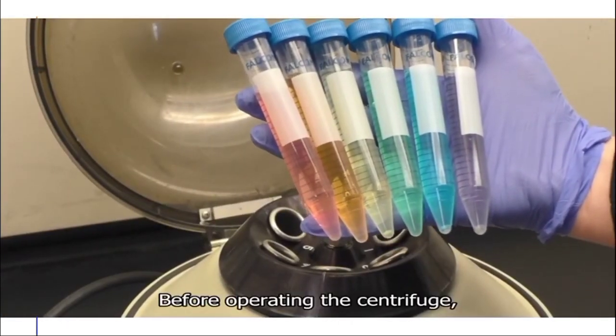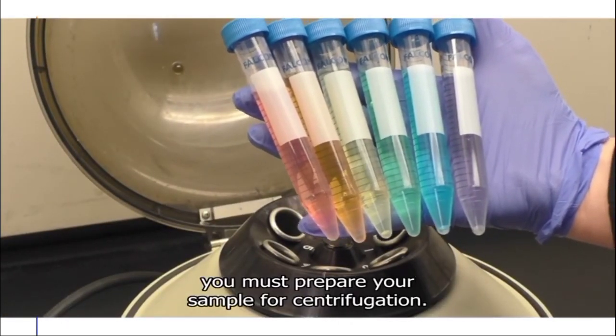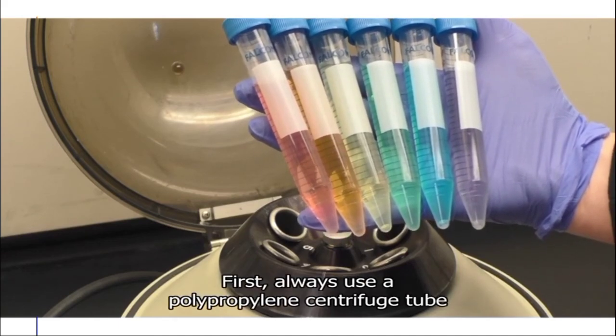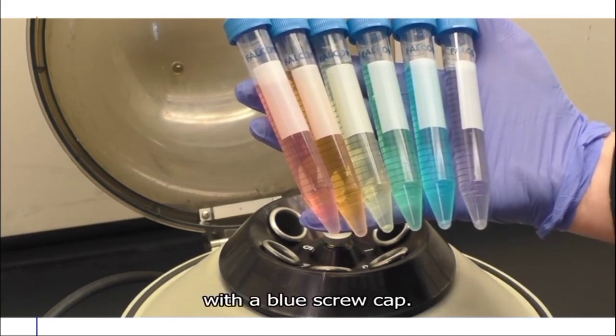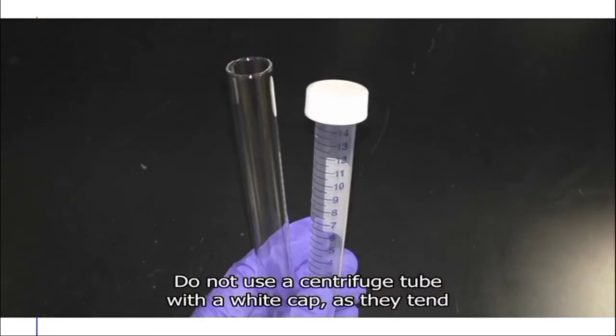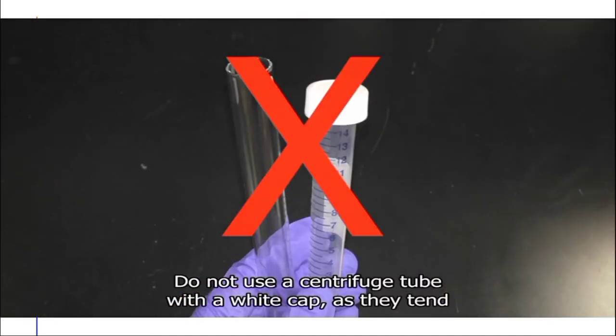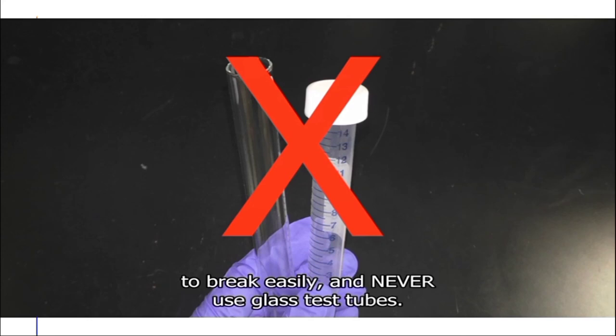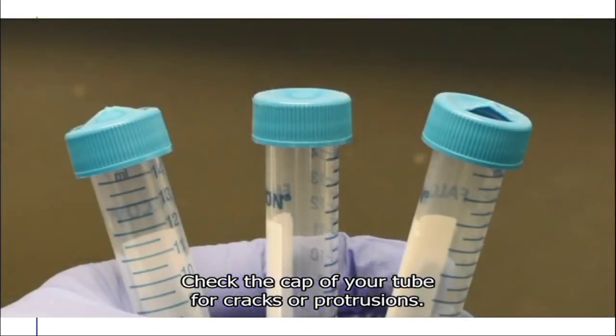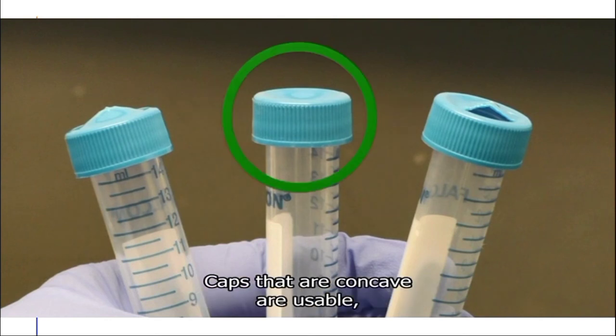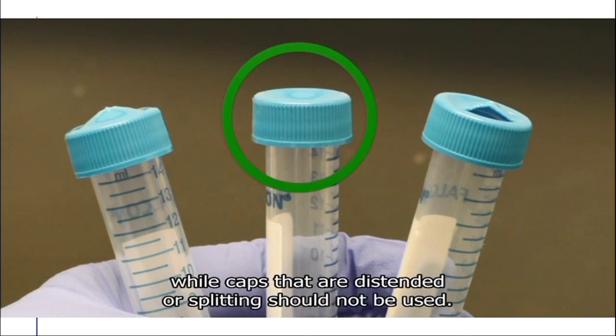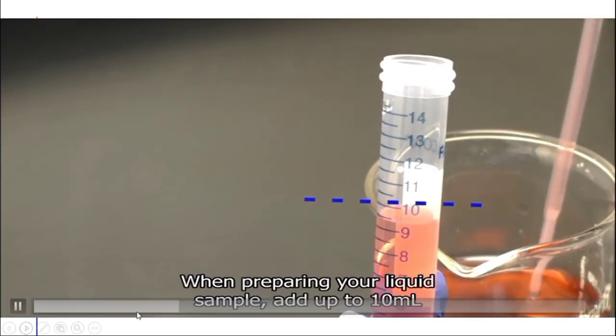Before operating the centrifuge, you must prepare your sample for centrifugation. First, always use a polypropylene centrifuge tube with a blue screw cap. Do not use a centrifuge tube with a white cap as they tend to break easily, and never use glass test tubes. Check the cap of your tube for cracks or protrusions. Caps that are concave are usable, while caps that are distended or splitting should not be used. When preparing your liquid sample, add up to 10 milliliters.